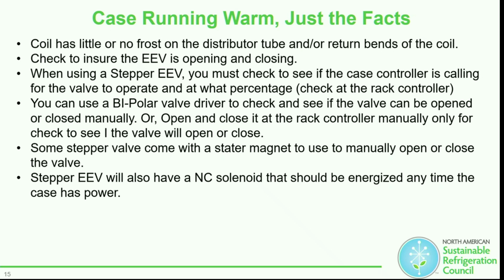A stepper EEV will also have a normally closed solenoid that is energized anytime the case has power. Also, a lot of the bipolar stepper controllers actually have a battery backup. So if they do lose power, just like the HPV and the BGV controller, which have a battery backup to assist in closing that valve when they lose power, a lot of these case controllers do have that as well.